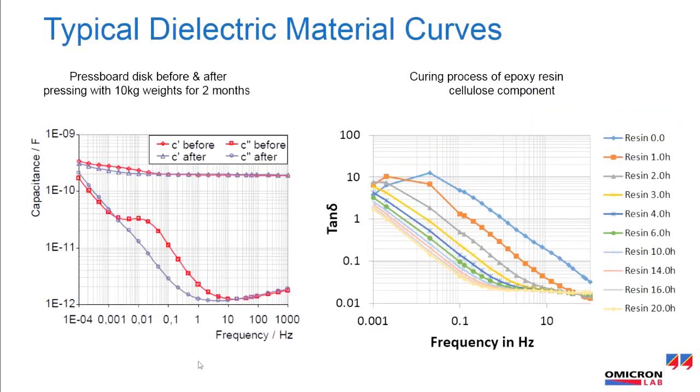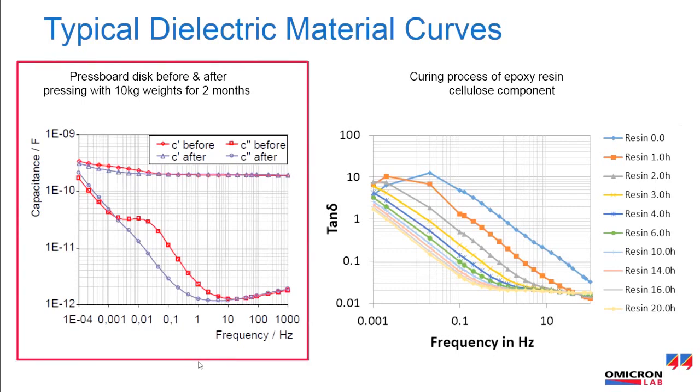These two curves also underline why it is important to measure over a wide frequency range. As can be seen in the first chart, it is often not enough only to measure the tangent delta.